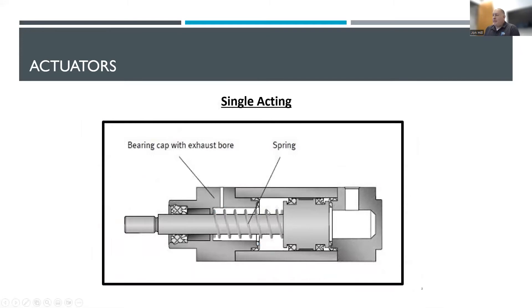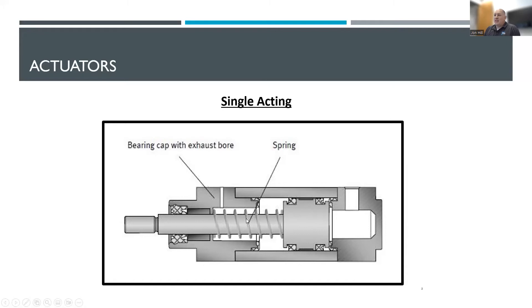With actuators, we have a couple of different types. A single-acting actuator typically has some sort of spring in it. Air comes in at the far end, pushes against the piston, and gives us motion out. When we're done with that motion, we release it to free air pressure and the spring overcomes that pressure and pushes the piston back. The amount of force this can generate is dependent on the area of the piston — the larger the piston, the more area you're acting on, which gives you more force.